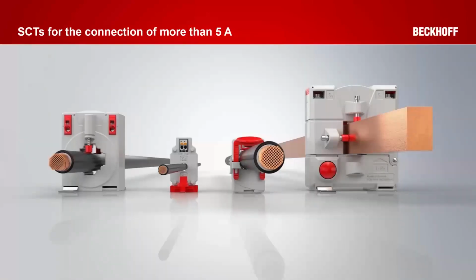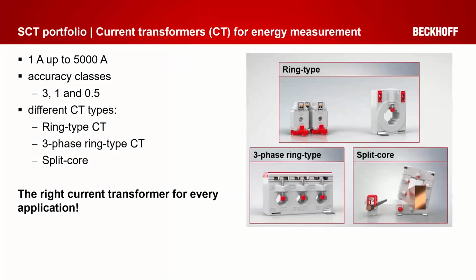To address this wide range of current measurement, we now have a new family. We call it the SCT family, or split current transformers. There are different housings and different concepts, from 1 amp up to 5,000 amp, and different accuracy classes up to 0.5, and different types. So we have the ring type here. We have them for one phase and for three phase, and for simple applications we have the split core transformers. So for your application, you will find the current transformer for you. Maybe we can also support you.